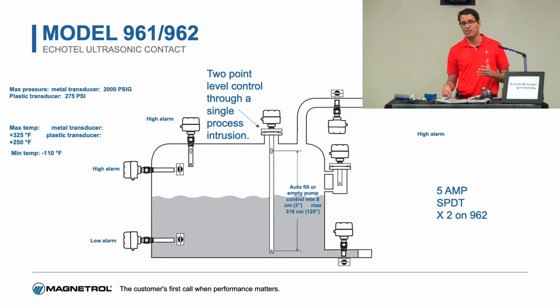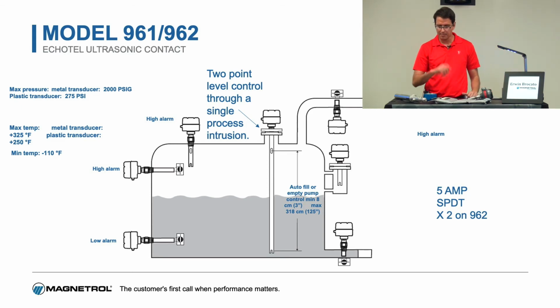This is the installation, how you can install them. For controls, you can do, like I said before, a low level, high level alarm like you see on the left here, or you can do a 962 on the opposite side here on the right. Your low and high level all in one device, which is pretty cool. That way you don't have to have multiple taps to the tank. You just insert it from the top and then you can do your controlling.